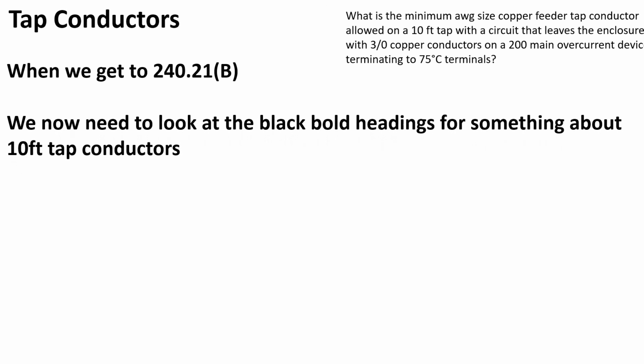All right, so now that we've caught up to this point, where you look at our black bold headings, we see right here in part 1, it's for taps not over 10 foot long. If the length of the tap conductor does not exceed 10 foot and the tap conductors comply with all of the following. So when the code book says all of the following, that means it's got to hit every point. We're going to briefly go over it, and then I'm going to take us down to our section. But if you were going through this for the first time, you might want to read every single one of these sections to the T as you're looking for your answer.